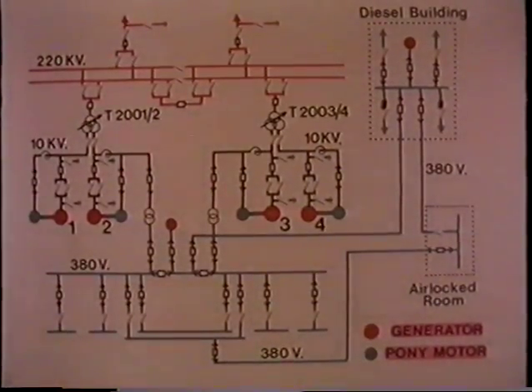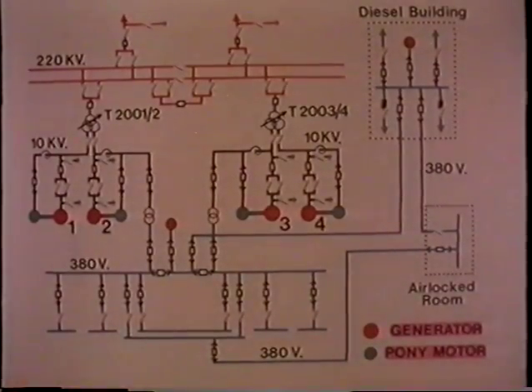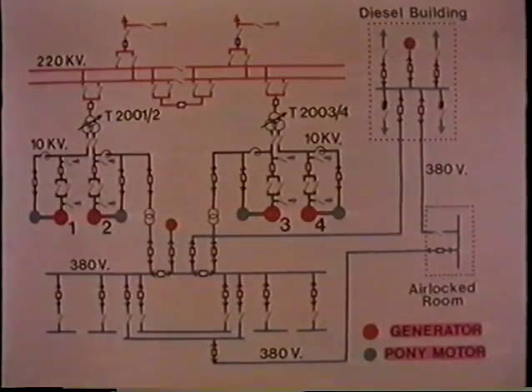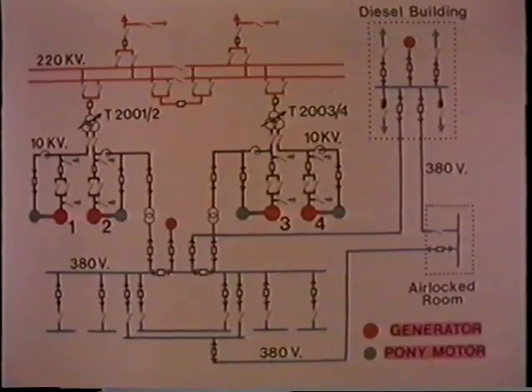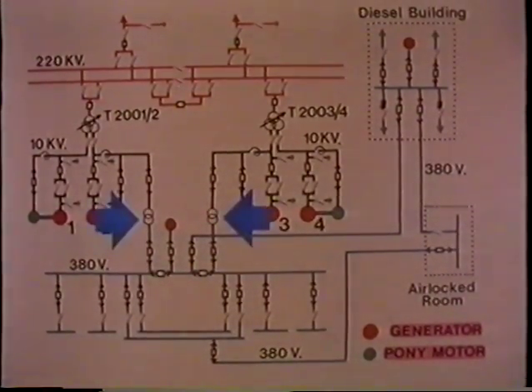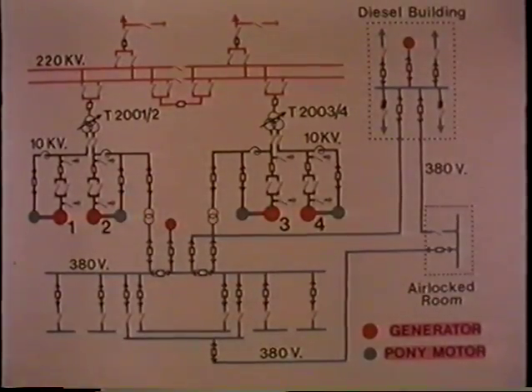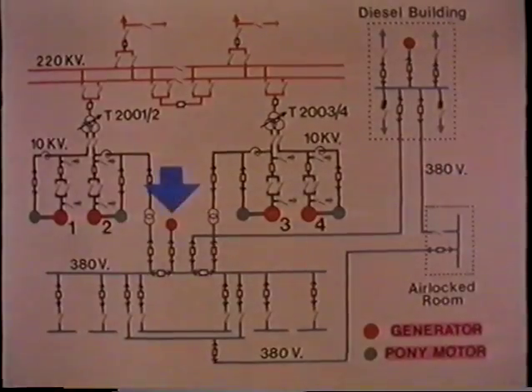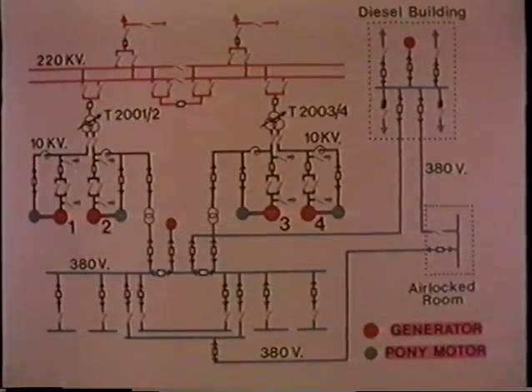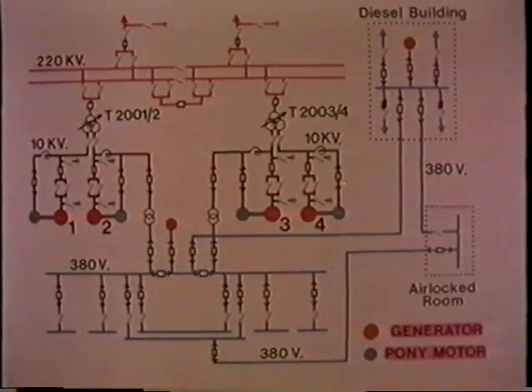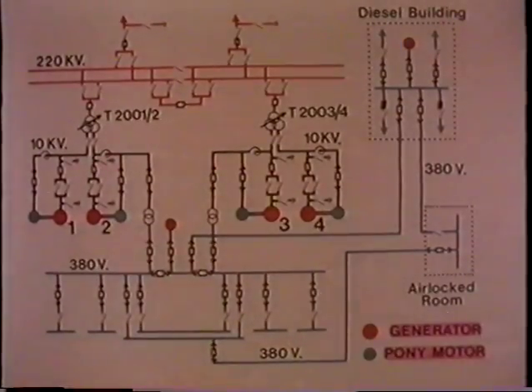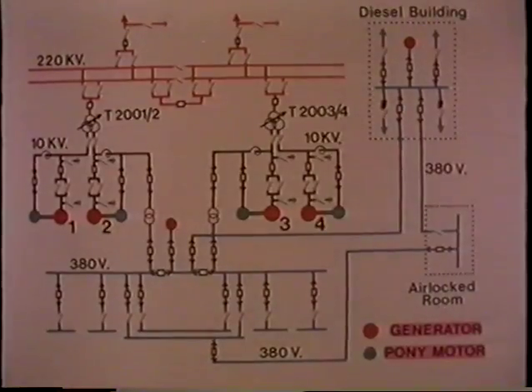This single-line circuit diagram shows all the main features, including the low-voltage supply to the station auxiliaries. Four possible sources of supply are provided: two fireproof unit transformers with automatic changeover, a 1000 kVA auxiliary turbine-driven generator, and a 590 kVA diesel generator.